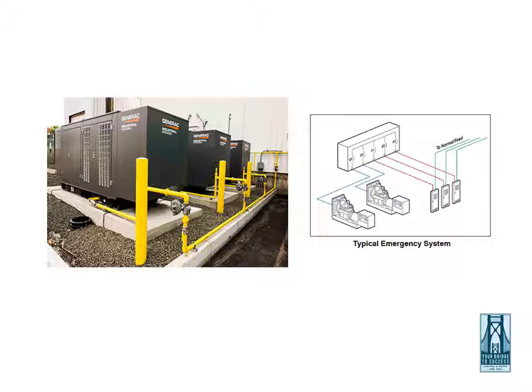In trying to stay with natural gas, eliminate larger units, and adding in some redundancy or future capacity, paralleling smaller generators is an option. In this scenario, the possibility of 300 kW units could be paralleled together to make up 900 kW of standby power and allow for servicing of 1 unit at a time while the other 2 carry the load.